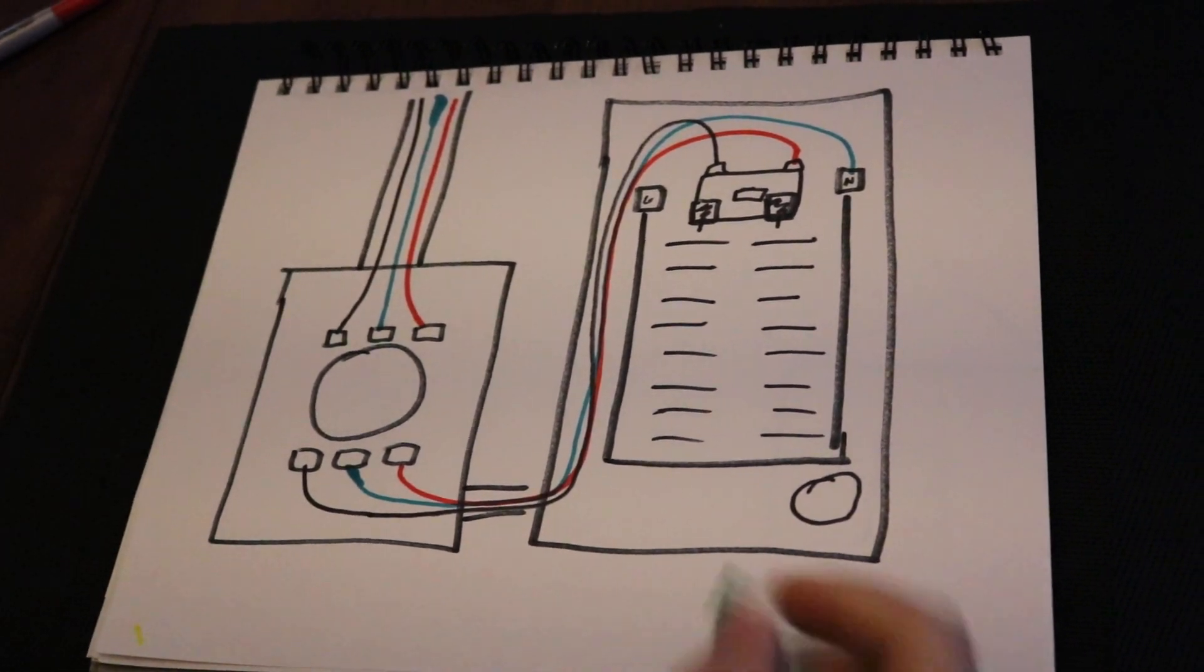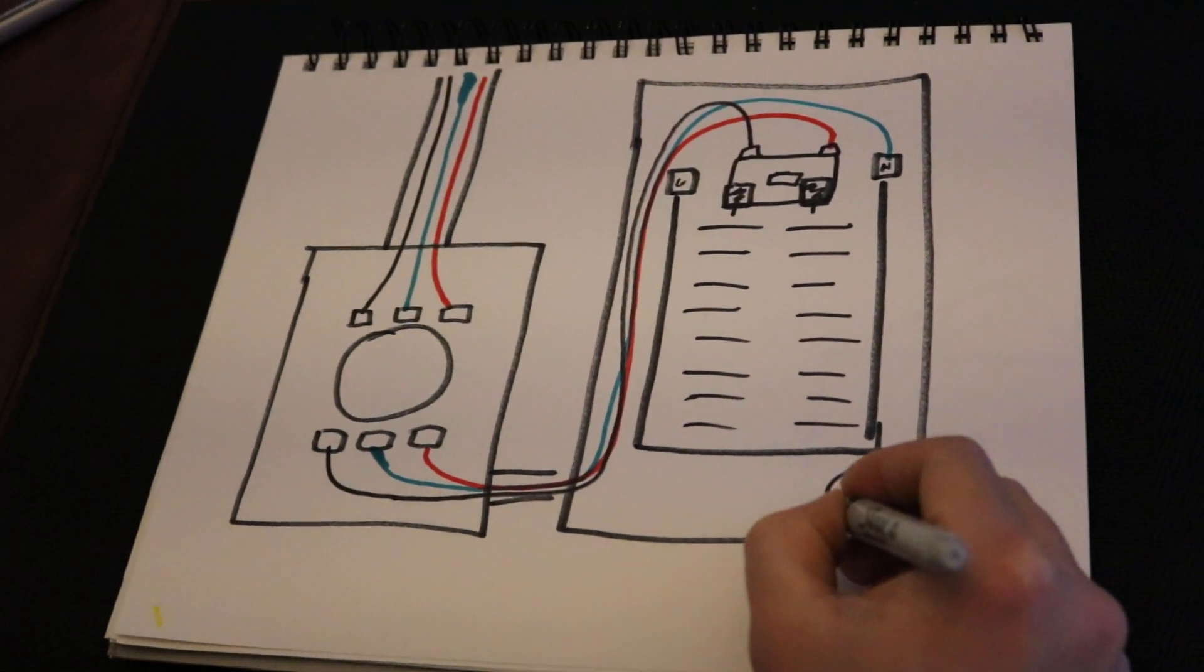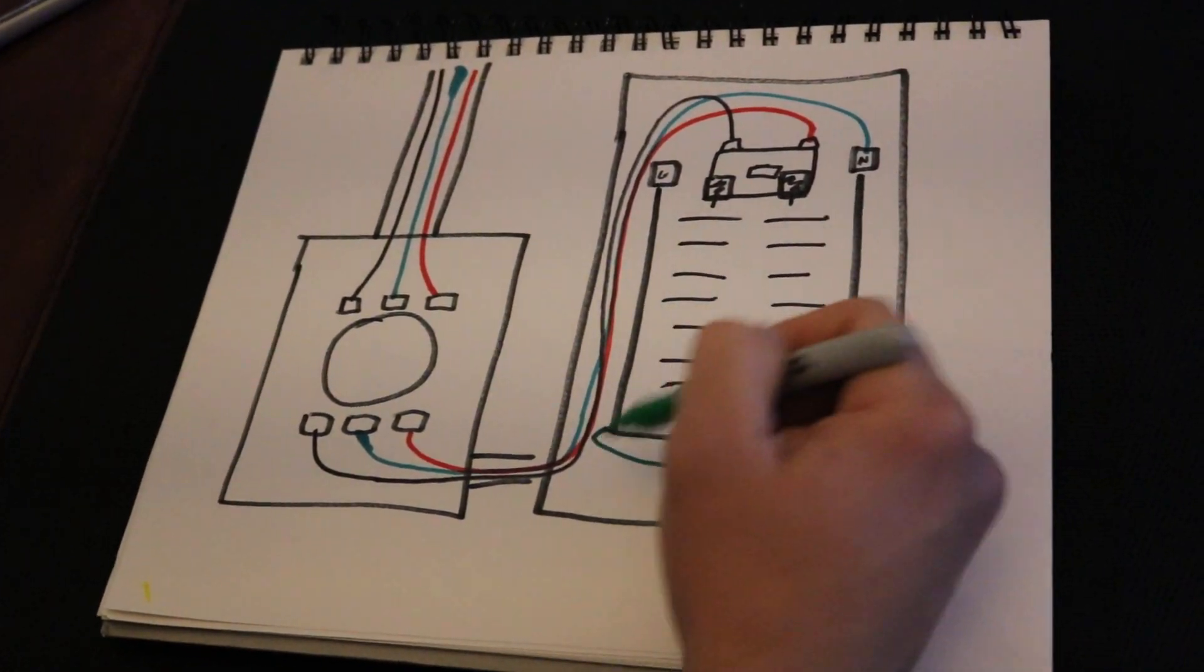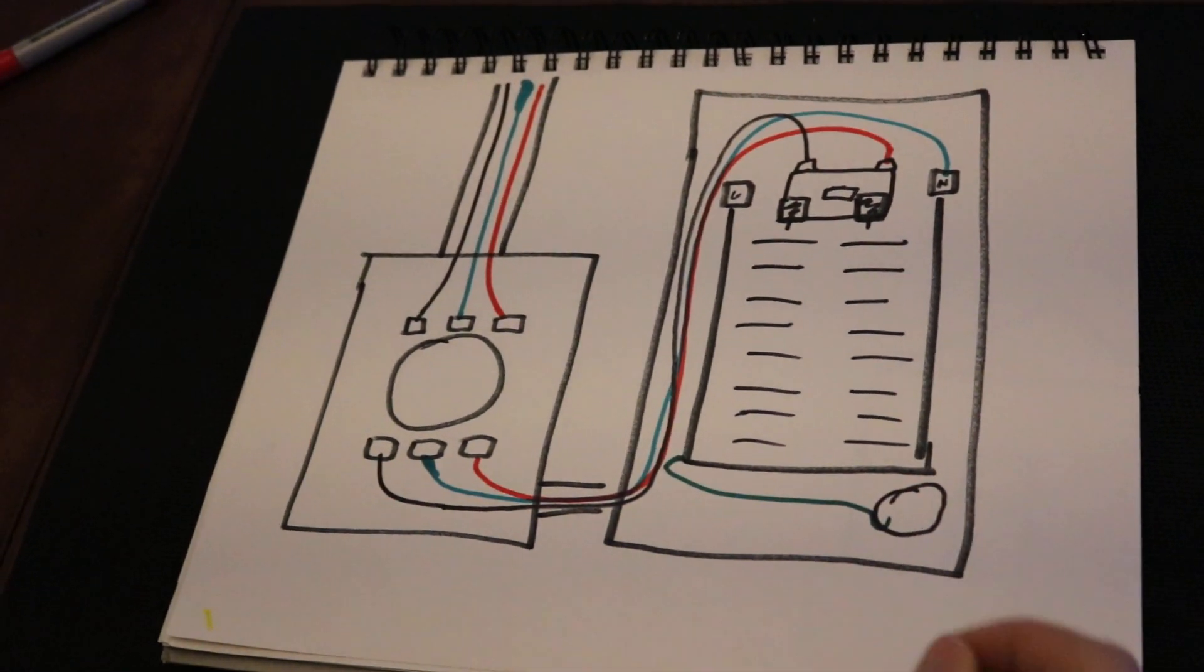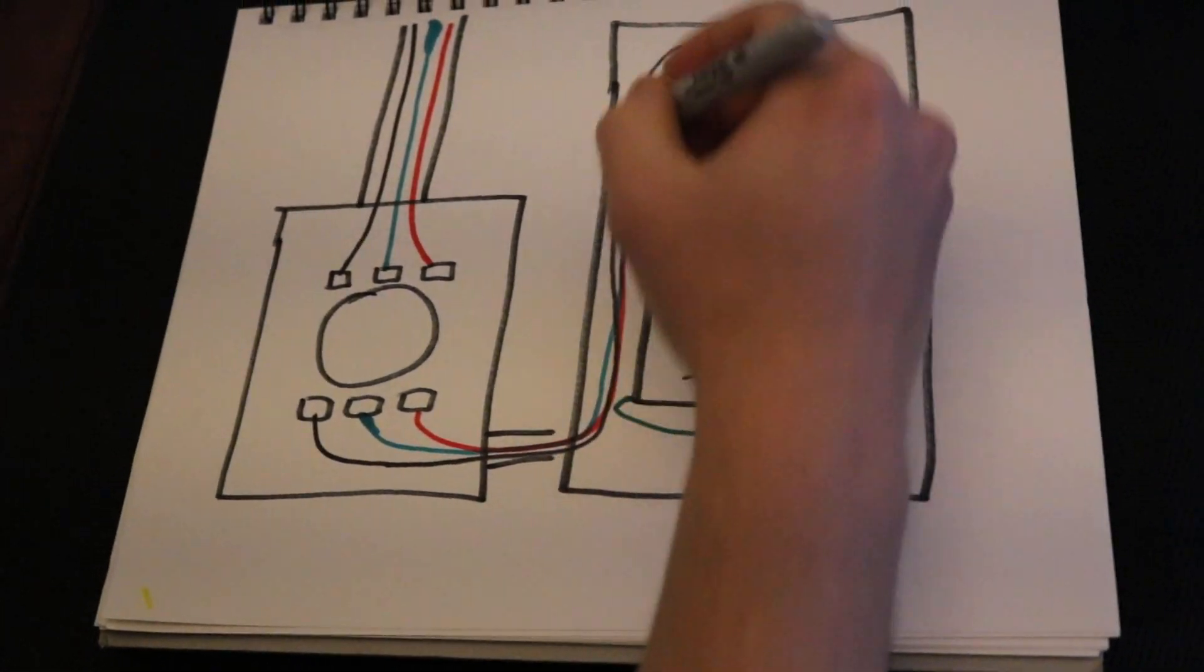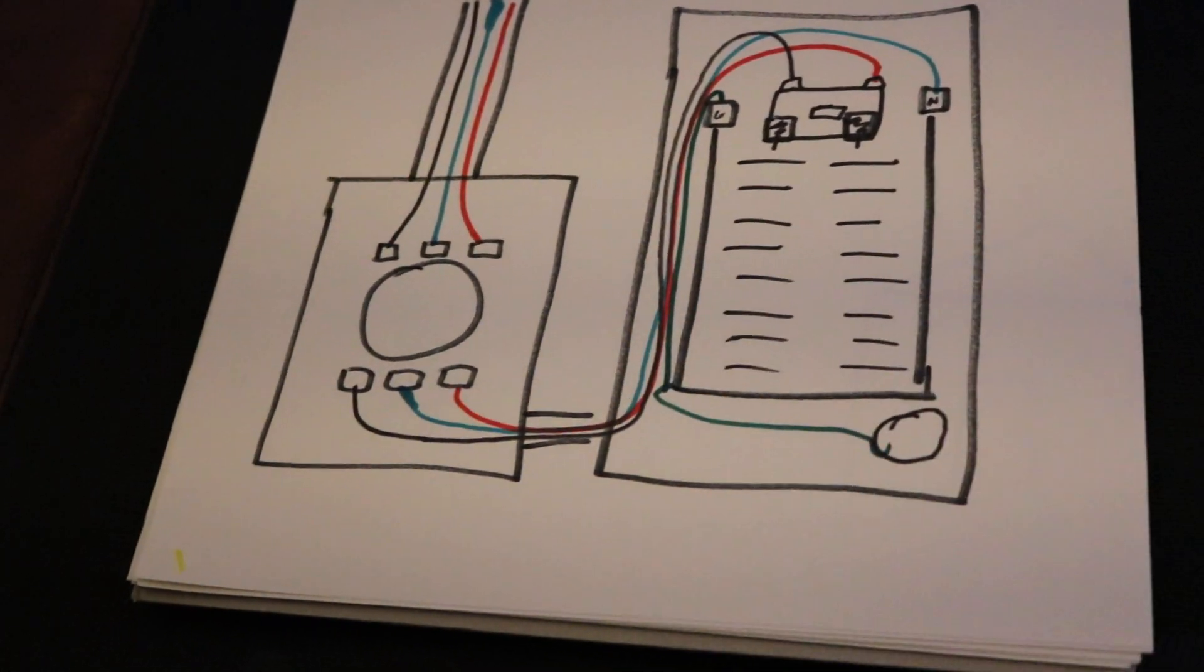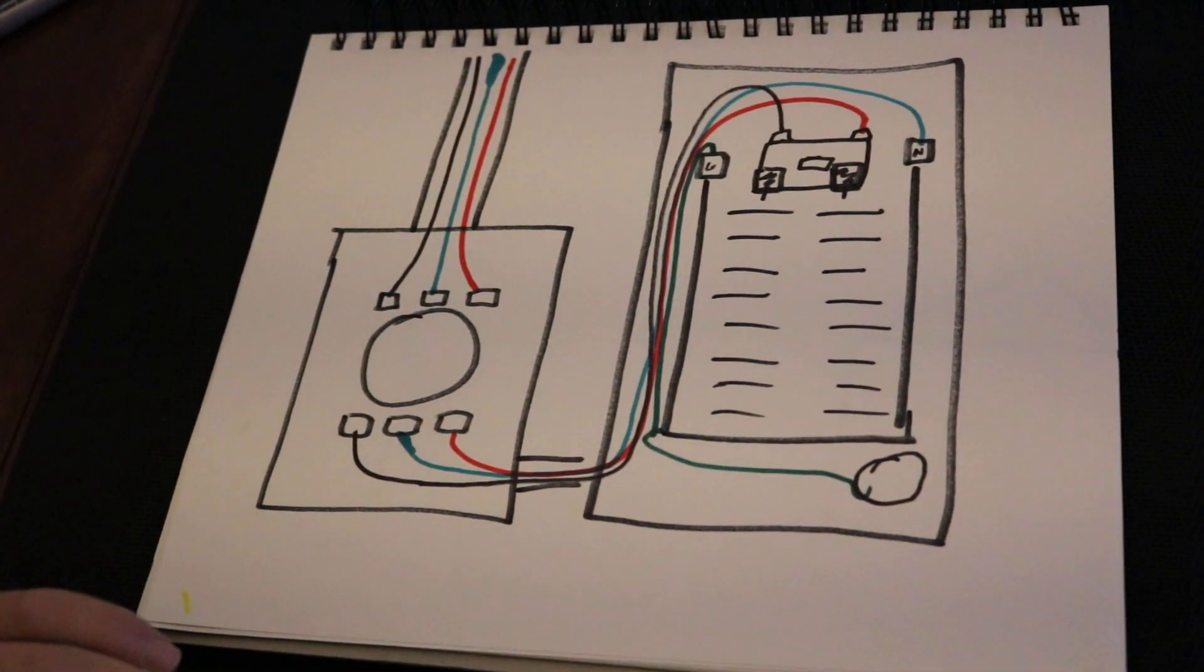Then you're going to have the ground wire. If you have a slab it's usually going to be a Ufer ground where it will come in here and connect to your ground bar. So the first point to disconnect, your neutrals and your ground bond. If you don't have a Ufer then it would come in from a ground rod down below and connect to this bar right here. Some panels have lugs, some don't. Your main disconnect is where your neutrals and your grounds are going to bond.